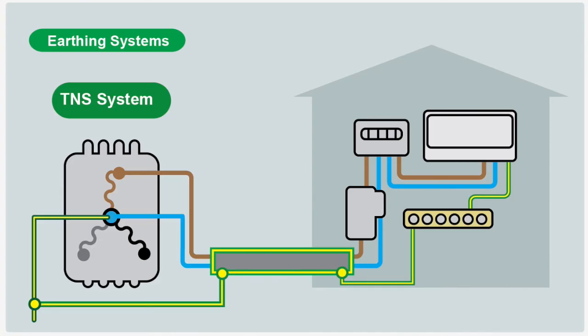The next type of earthing system is known as TNS. This time the distribution people do supply an earth, and it's often on the sheath of the supply cable.